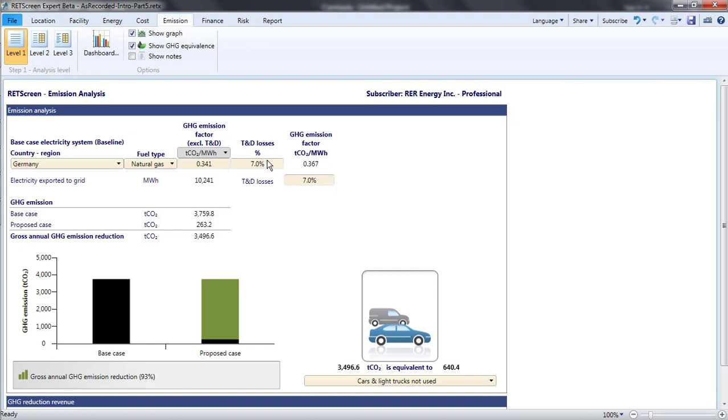To find this, the user specifies the percentage of generation that is lost in the T and D system for the baseline and for the proposed case. 7% is a good starting point for a well-designed and maintained grid.